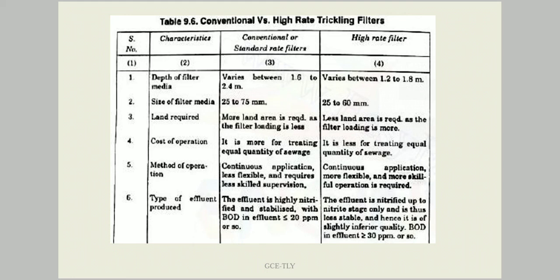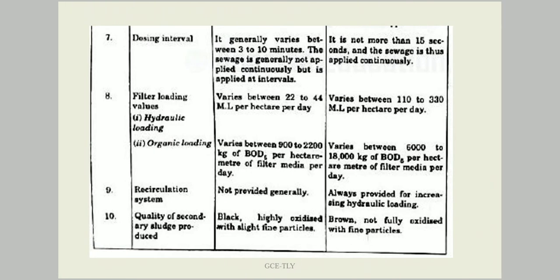The method of operation for conventional trickling filter is continuous application of water, less flexible, and requires less skilled supervision. For high rate trickling filtration, the continuous application is more flexible and requires more careful, skillful operation. The type of effluent produced is highly nitrified and stable in case of conventional trickling filter with BOD less than 20 ppm. In high rate trickling filter, the effluent is nitrified only up to the nitrite stage, is less stable, and BOD is greater than 30 ppm. Dosing interval is 3 to 10 minutes for conventional and less than 15 seconds for high rate filters.